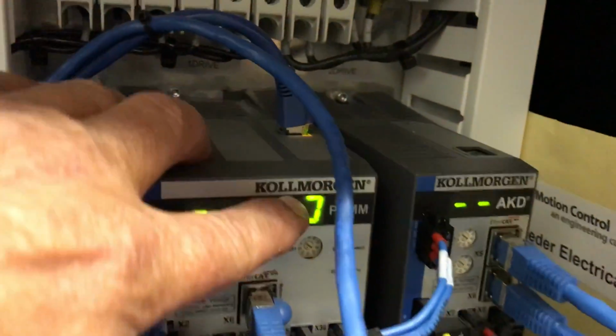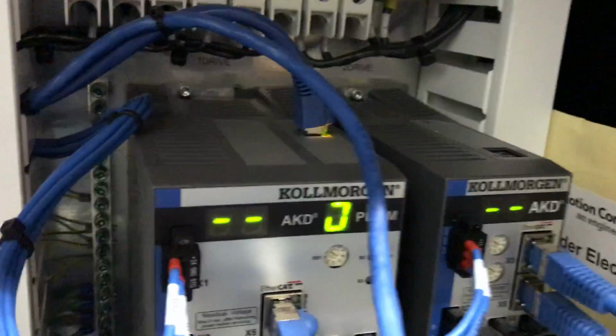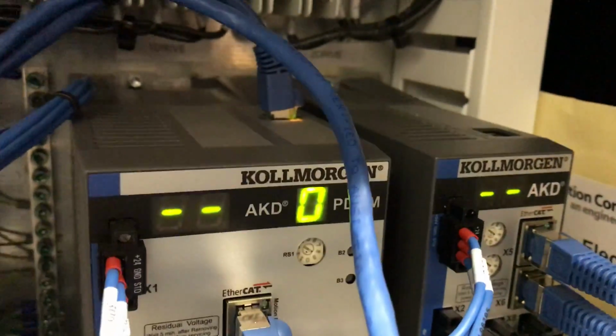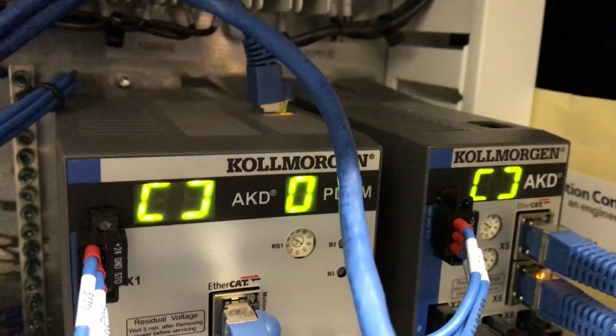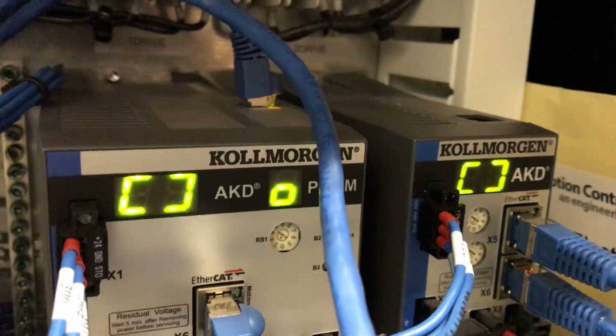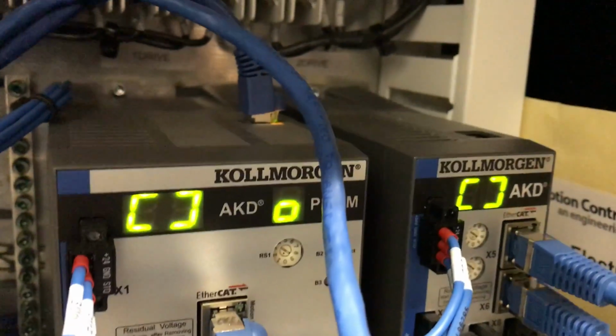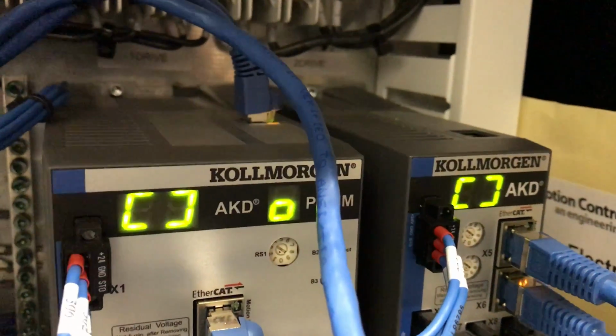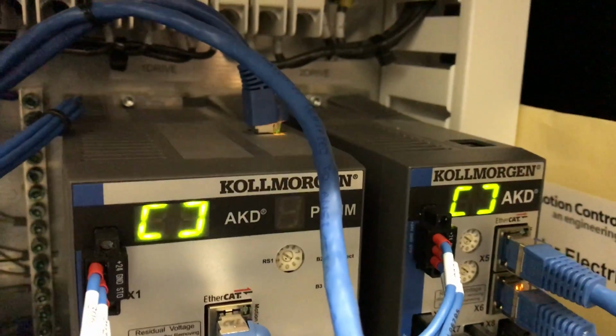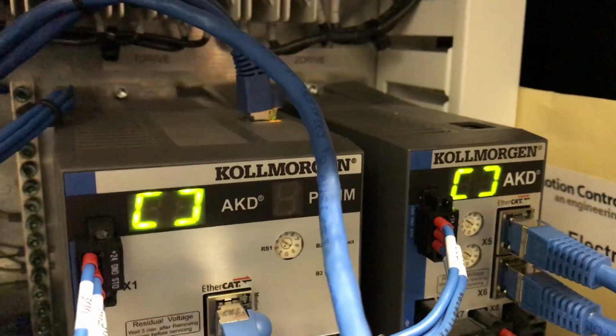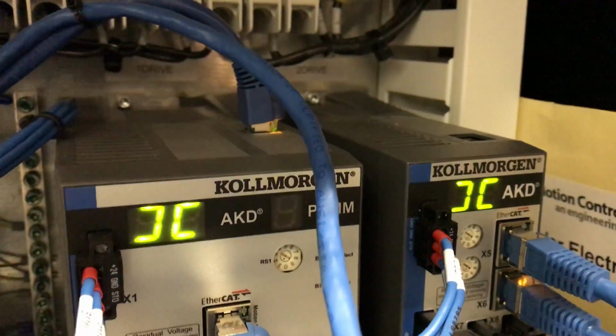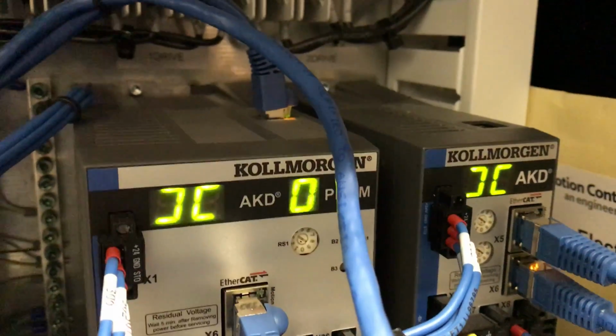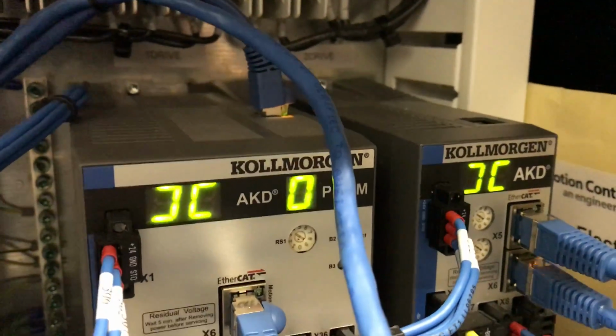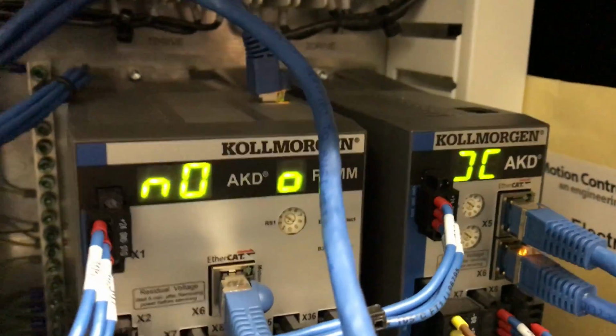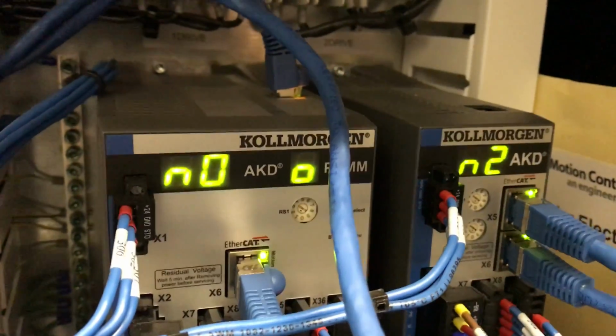There's also some information that's displayed in this area. And the first thing that's going to be displayed is the IP address of the drive during the boot. So we'll watch that. And in a second, we'll see the IP address flash by. IP 192.168.50.101. So that's the IP address of the drive.